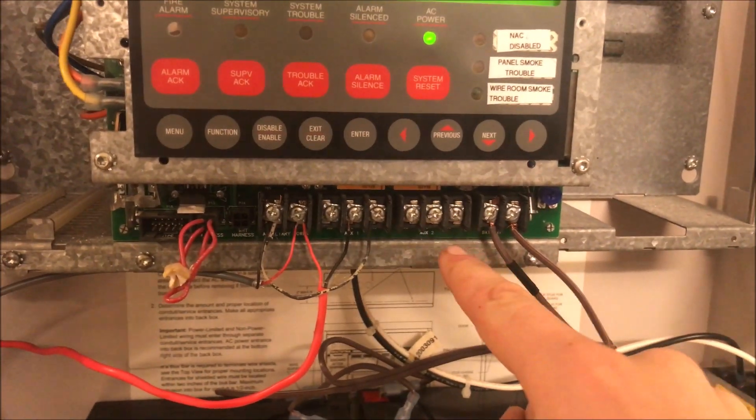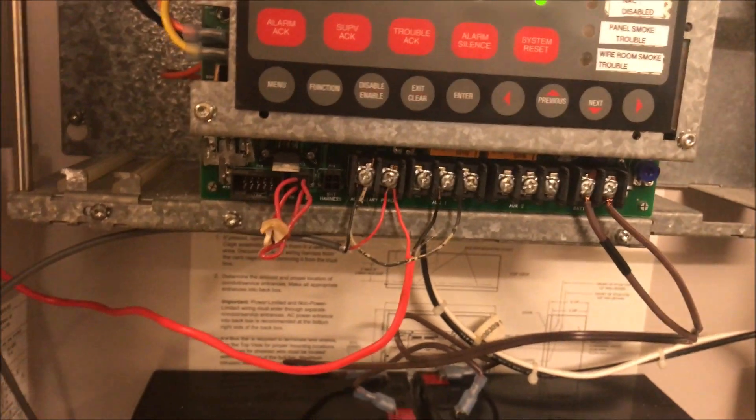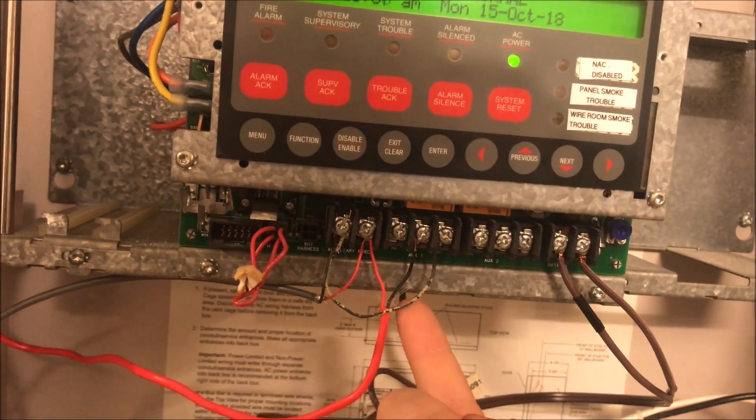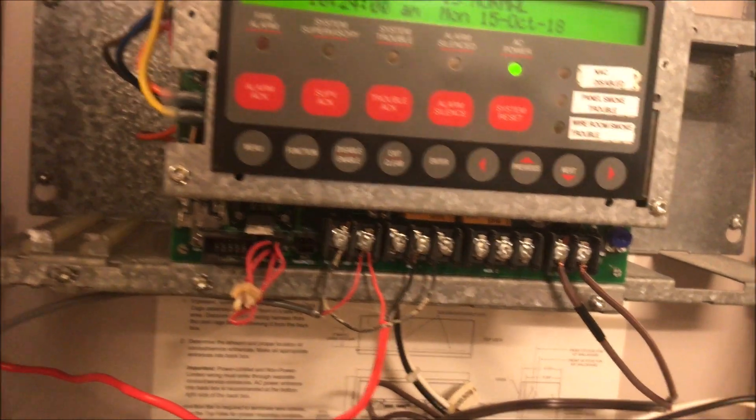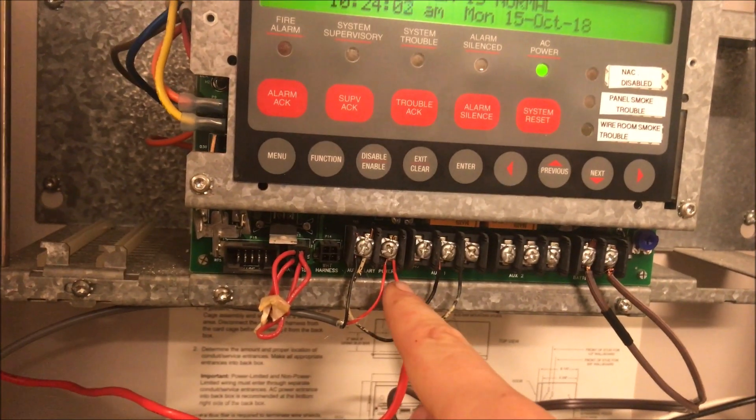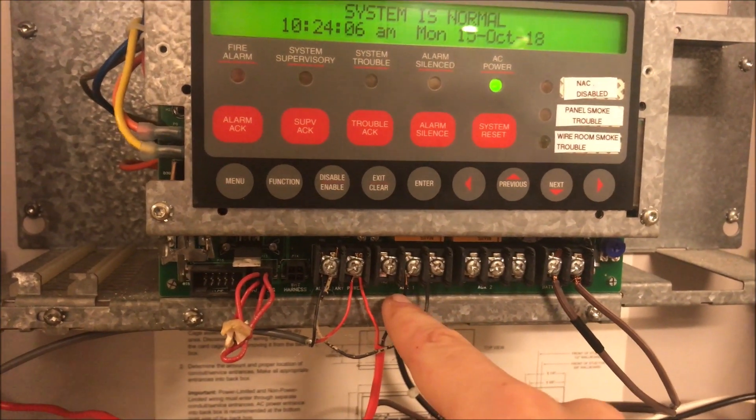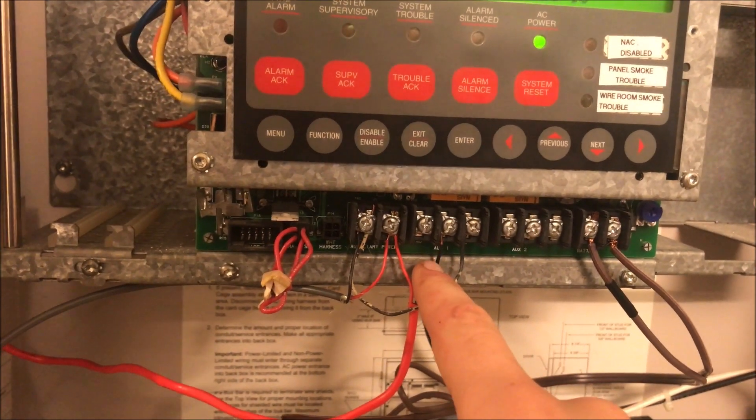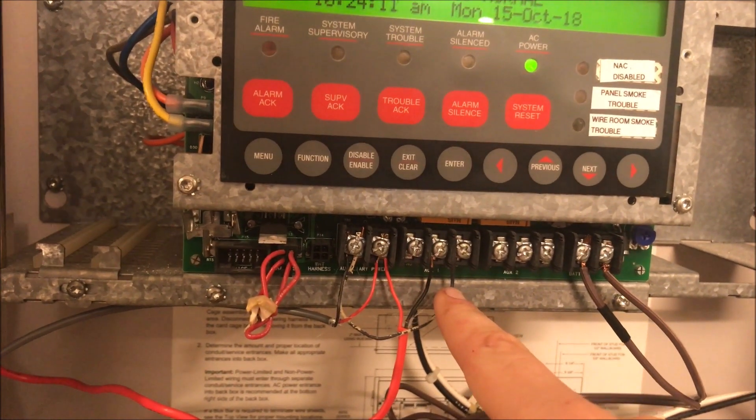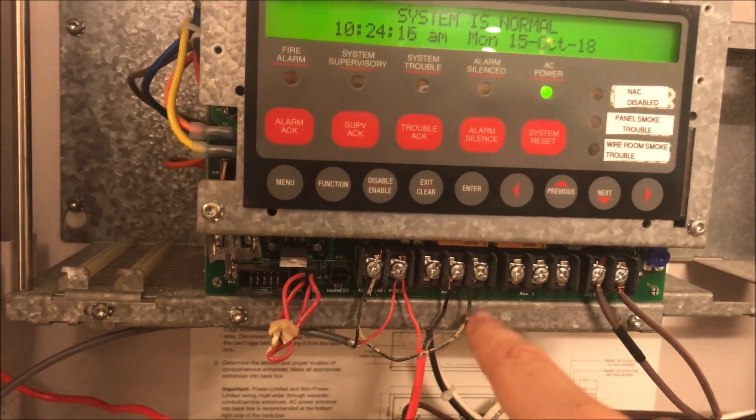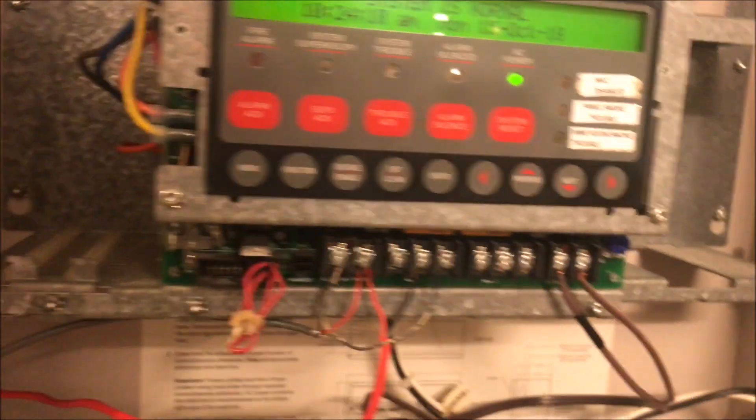These two blocks of three terminals are your relays. You have two auxiliary relays—normally open, common, and normally closed. This one is being used for my door holder. I have positive coming from the auxiliary power, and the negative is what's being cut through the relay. So you have your negative coming in from auxiliary power, and that gets cut between the relay. Over here is the same block of relays.